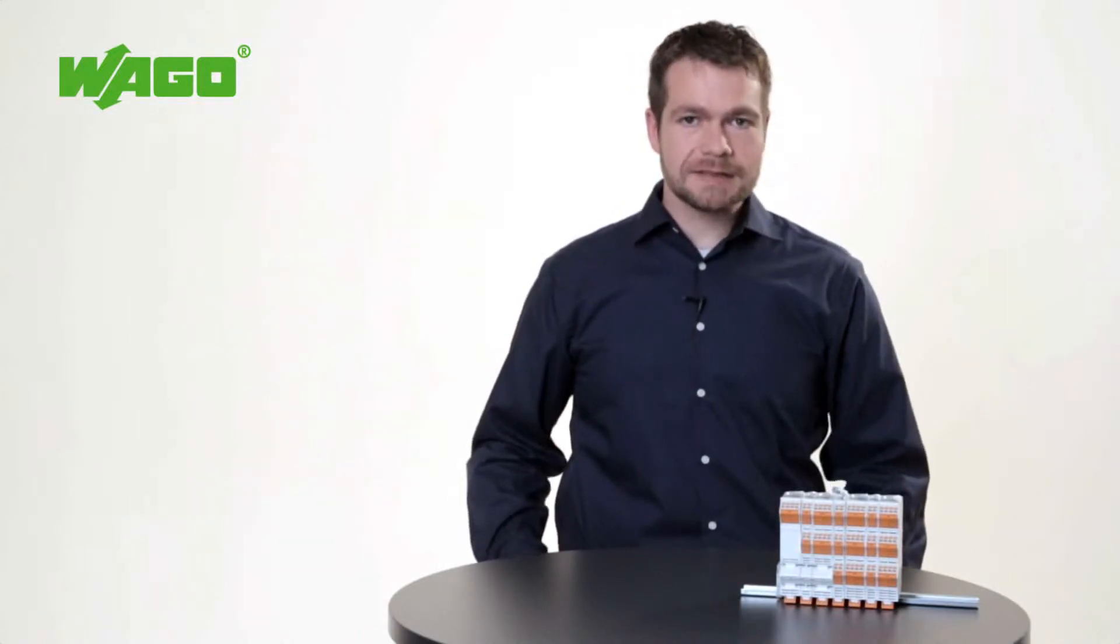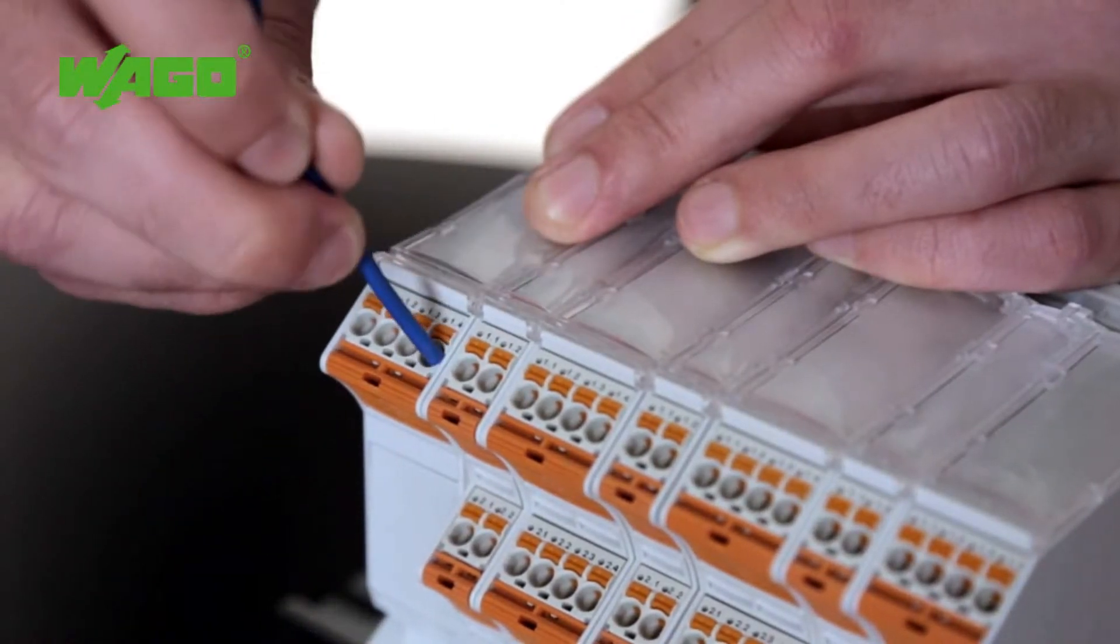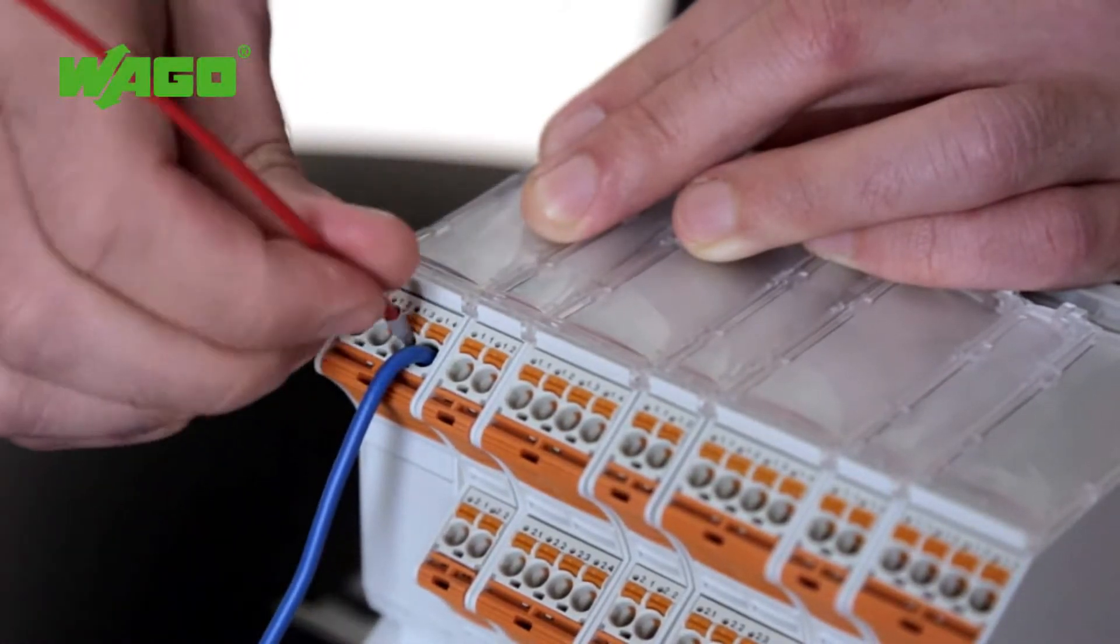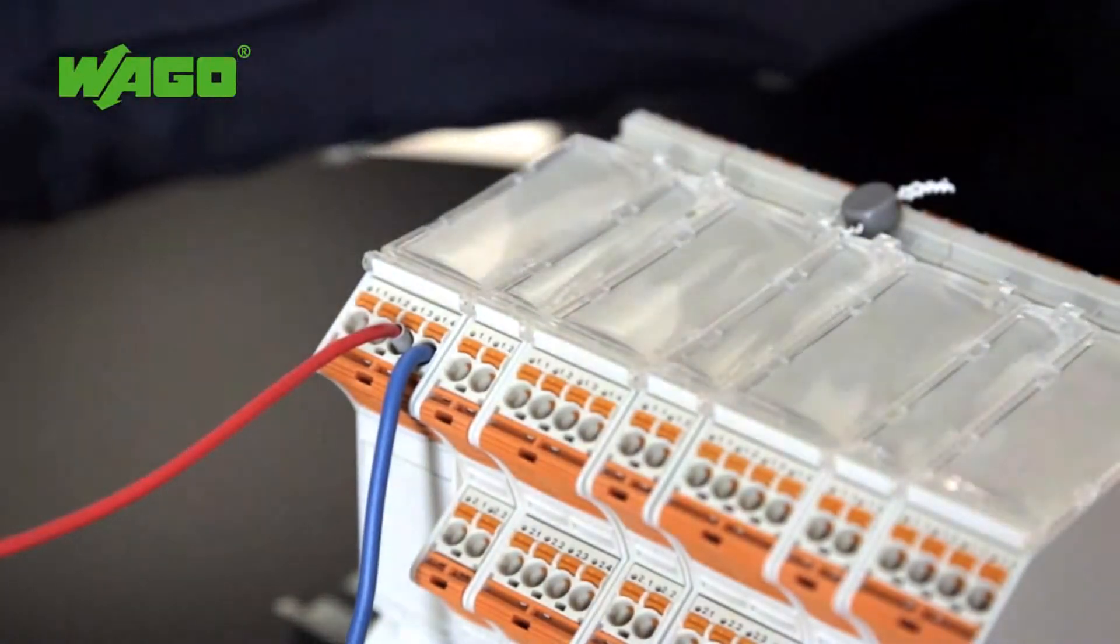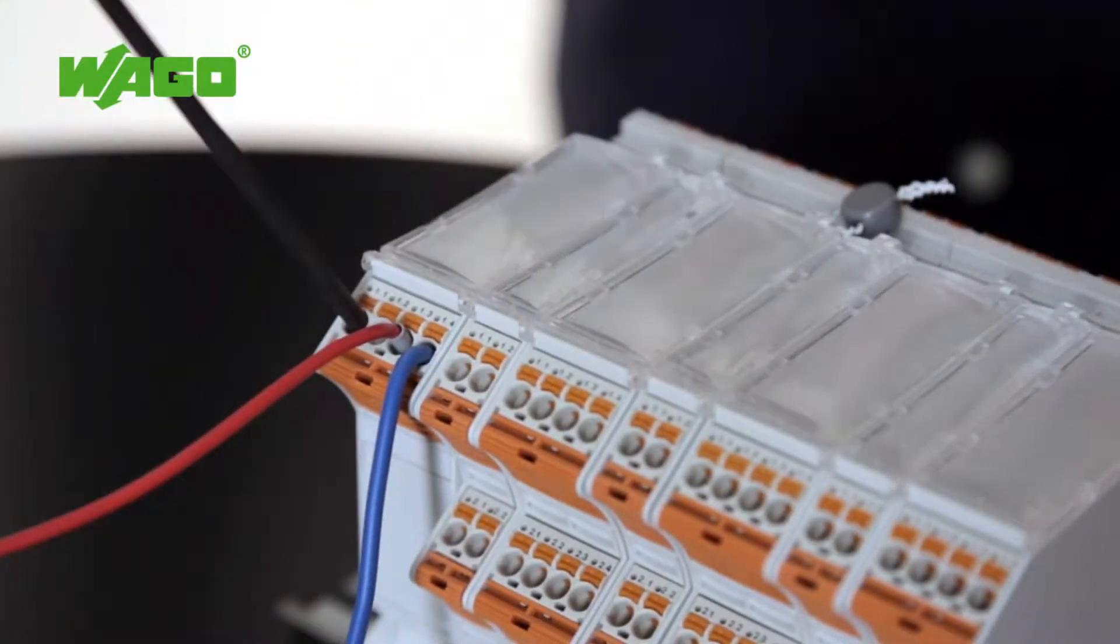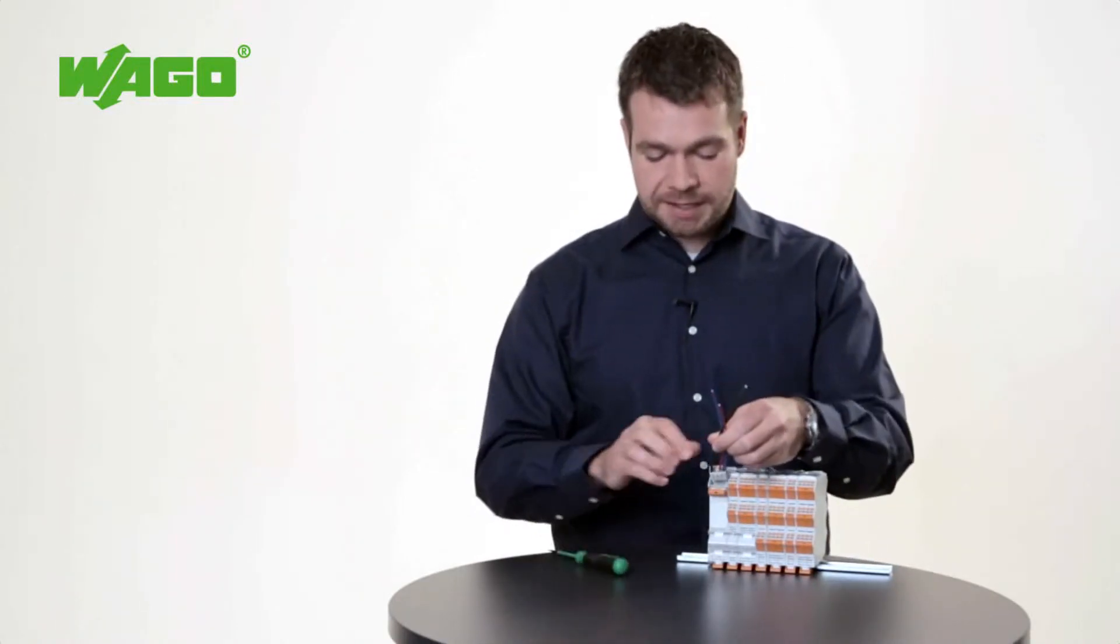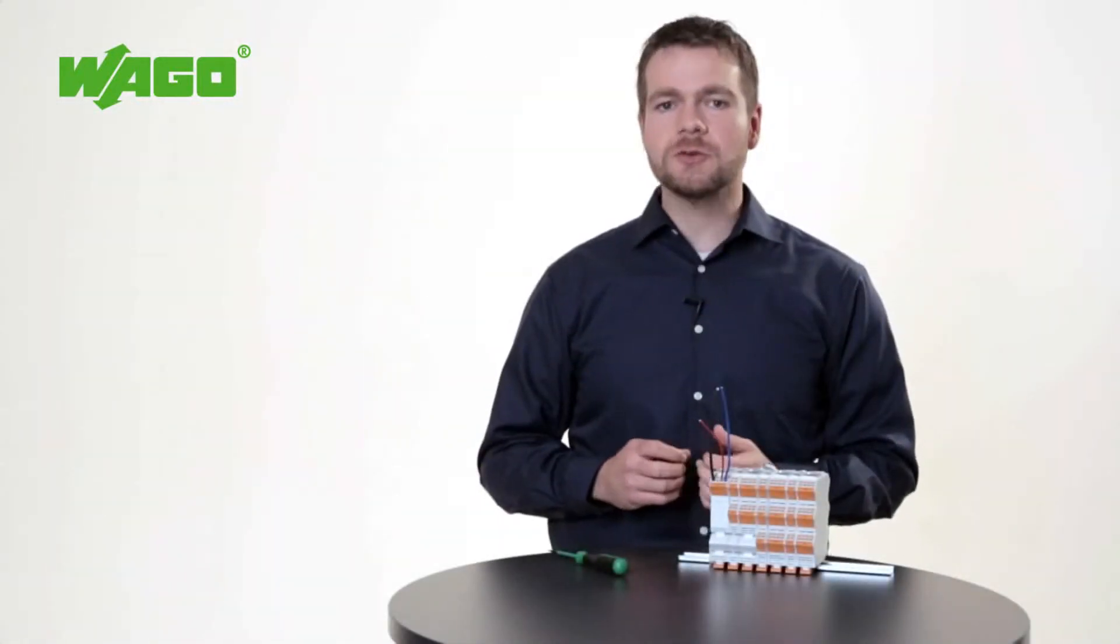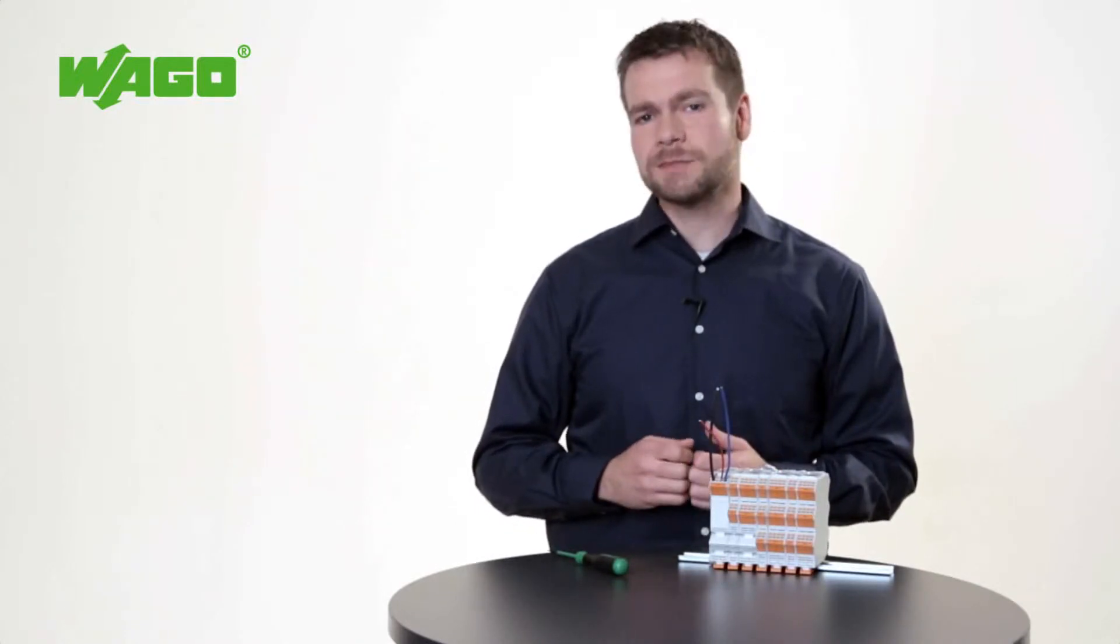Conductor termination also provides you with numerous options. Both solid and ferruled conductors are connected by simply pushing them into the unit. Fine-stranded, unferruled conductors are terminated via push-button actuation. Operation of the pluggable PicoMax connector is easy even when all conductors happen to be terminated. Furthermore, the wide cross-section range from 0.2mm up to 2.5mm provides you with a high degree of flexibility.